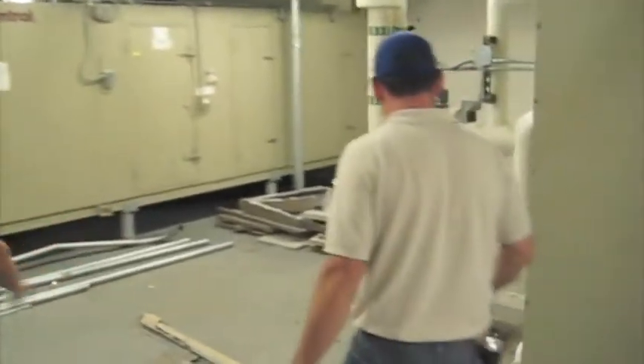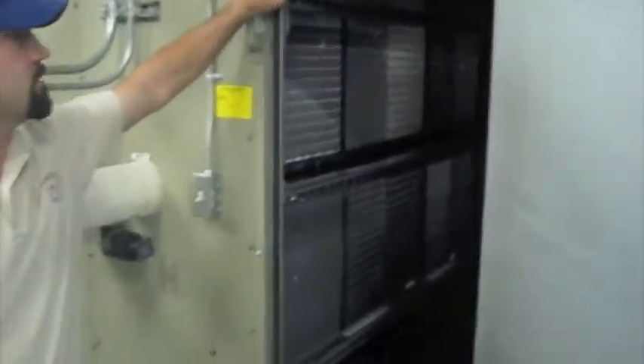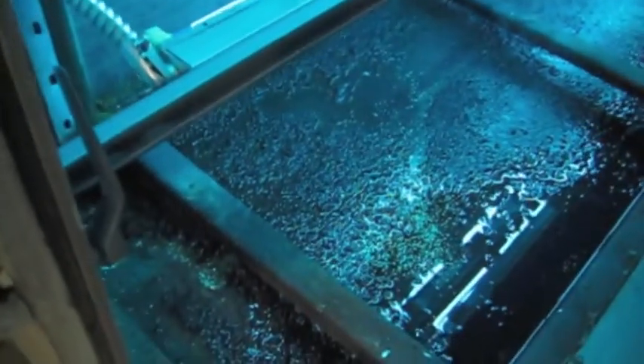This is a month and a half after those pictures were taken. In our equipment, we always shut off and switch off because this stuff will burn you — it'll burn your skin, it'll burn your eyes if you're not careful. I'm going to turn it on just for a second for the camera's sake so you can see the difference. You'll see all the residue in the bottom. This unit was not condensating at all when we started this test. Now this unit is actually putting out more condensation than units with coils almost twice its size. If you look closely, you will not see the discoloring stains running up and down the coils, and all of those small particles — those are the things being washed out. All of that stuff in the drain pans is the bio-organisms and micro-organisms that were growing on the coils; now they are dying and being washed down the drain pan.